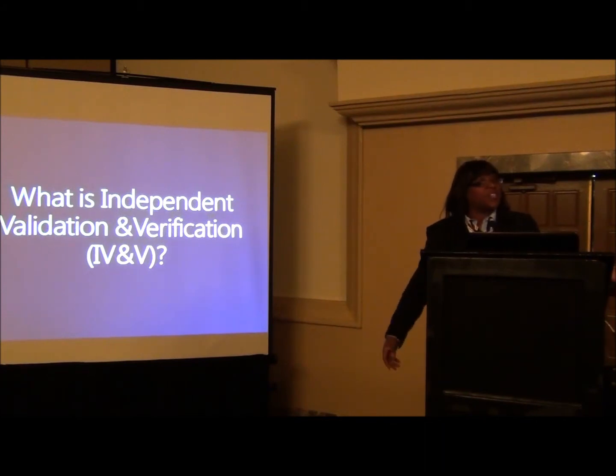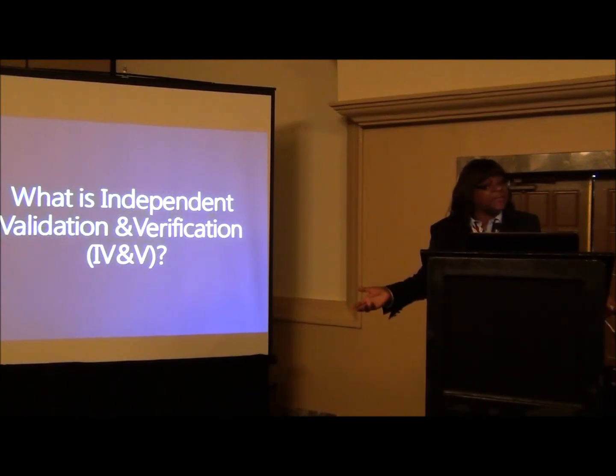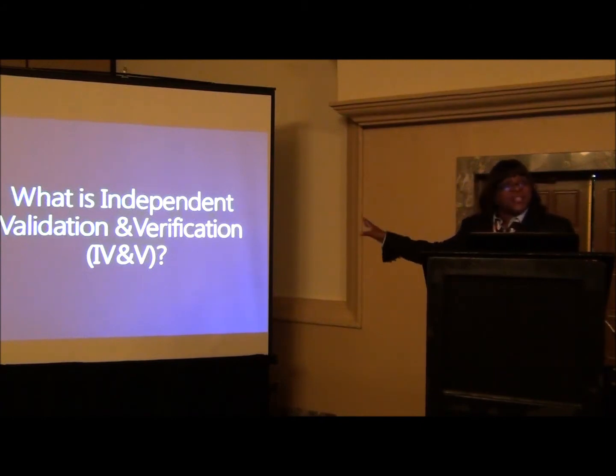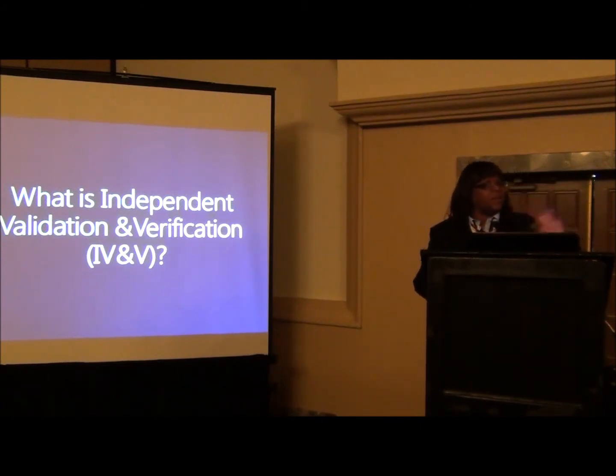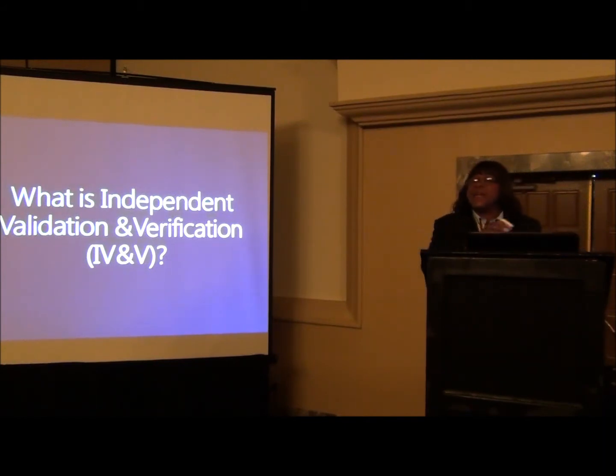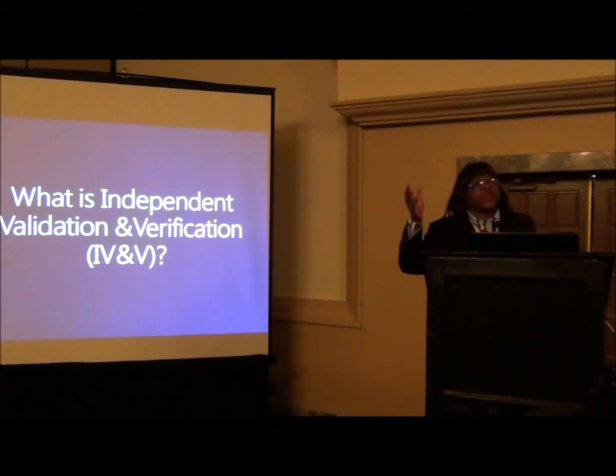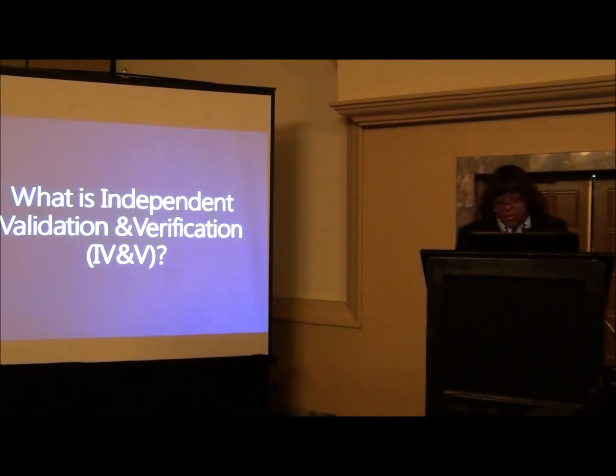Why? Because you're actually confirming the obvious. If you built it, of course you believe it works — it's not objective. The FDA won't accept it. When you look at validation and verification, the first principle you have to understand is that validation has to be conducted independently. You need an independent partner to work with you on validation. If you're the integrator, you can't validate your own product.